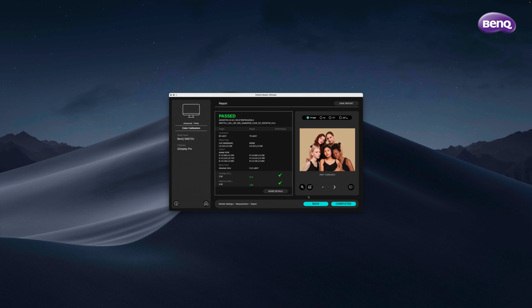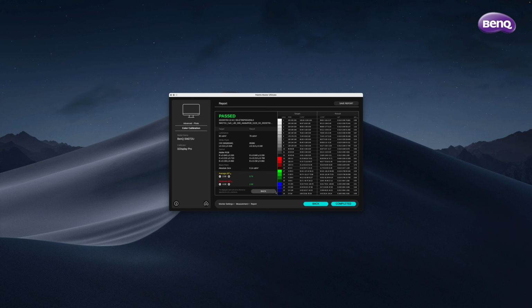And once our calibration is complete, we get a calibration complete notice, and we can check the report. And we can see here straight away that the monitor has passed. It has a fantastic result here actually. We asked for 80 candelas, we got 79, that's extremely good. We asked for 6500 degrees Kelvin, we got 6508, that's also absolutely outstanding. But what is absolutely really amazing is that we got a delta E of just 0.74. That is phenomenal performance.